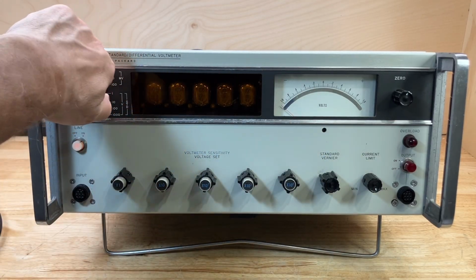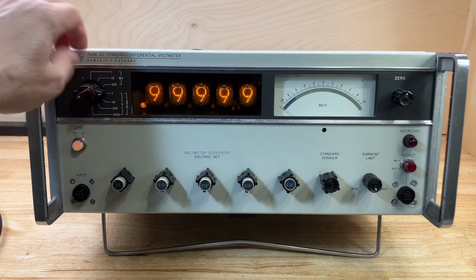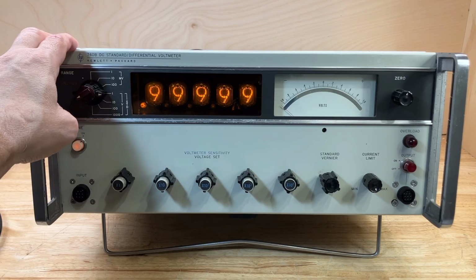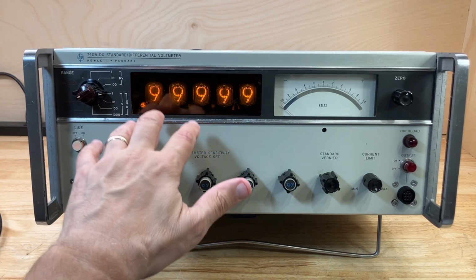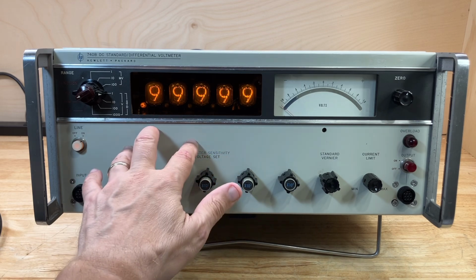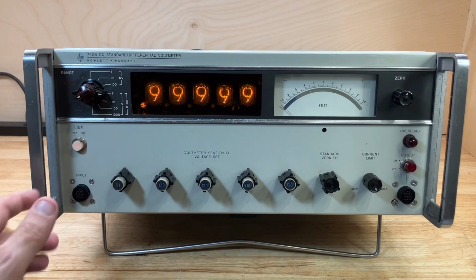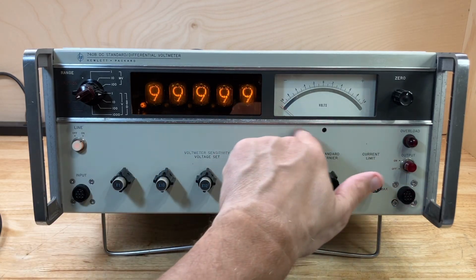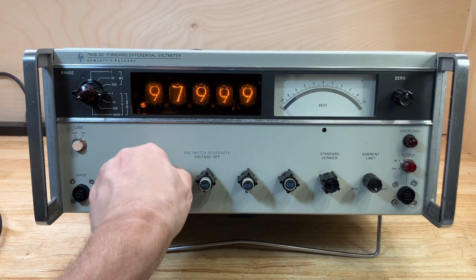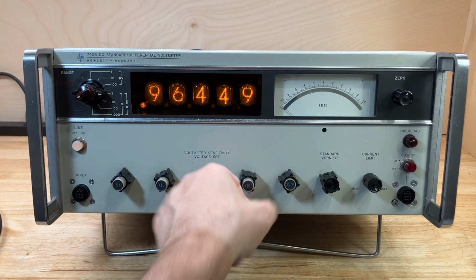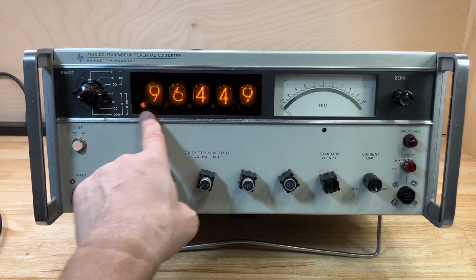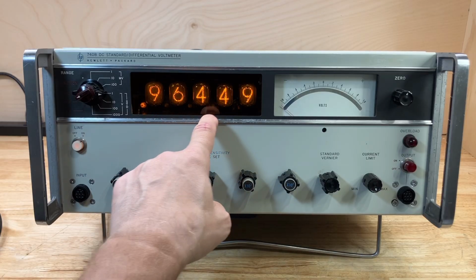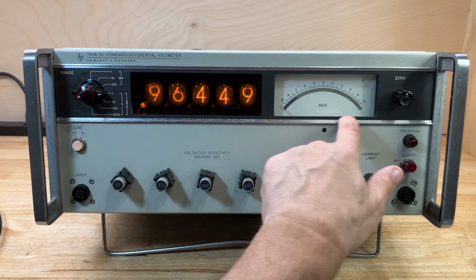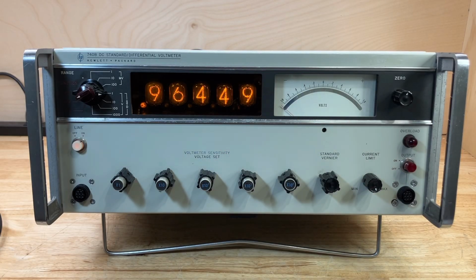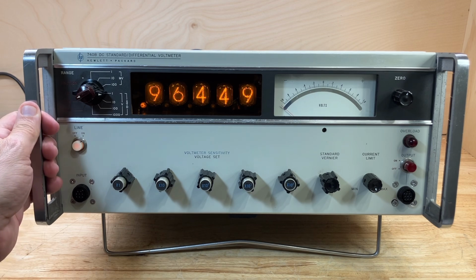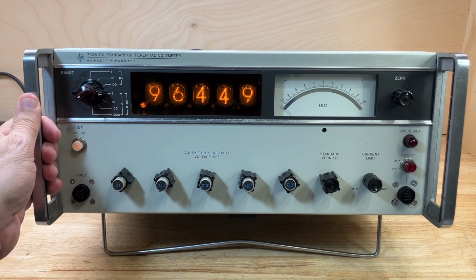It can also operate as a DC differential voltmeter, and what it will do in that mode is compare the voltage of the DC standard that's internal to the instrument with an externally applied DC voltage, and the meter will indicate the difference between those two voltages. So you dial the DC voltage from the standard until the difference between the two is 0, and you read the voltage of your unknown voltage directly off the Nixies with the final digit of resolution read directly off the meter. So that's the differential voltmeter function of this instrument.